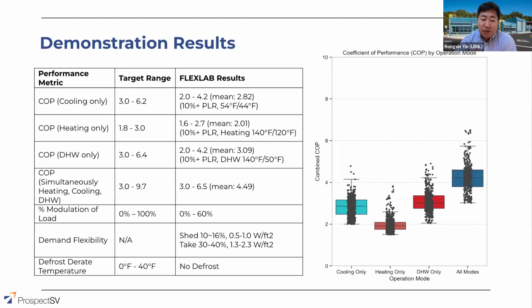But you can tell that for the individual mode, cooling only, the COP ranges between 2 and 4, and the average cooling COP is about 2.8. For the heating only operation mode, we have a range between 1.6 and 2.7, and the mean is 2.0 for the heating COP. And we have very good performance for the domestic hot water because there is a large delta T between supply and return: we have supply at 140 and return at 50. Although we tested a few days with supply up to 160 and a few hours at 180, that was just for capability testing, to see how high the temperature can go for the domestic hot water.